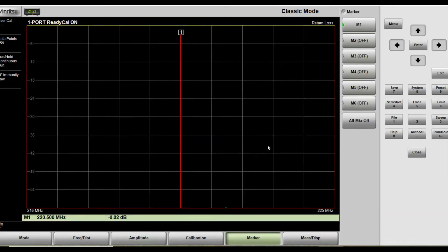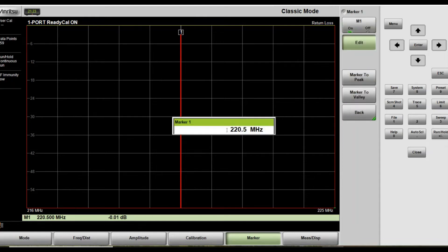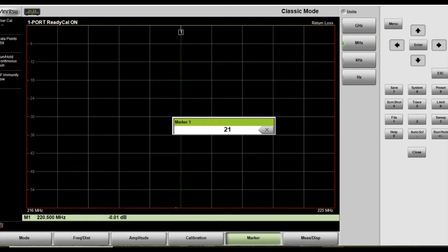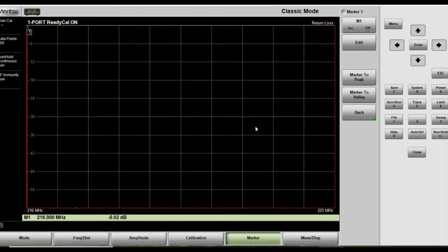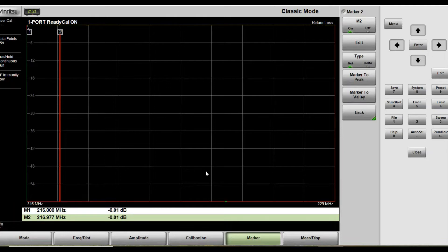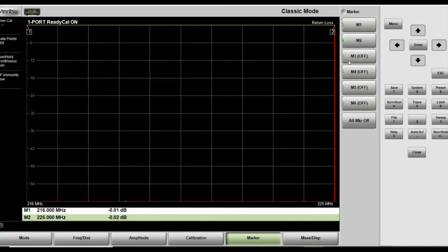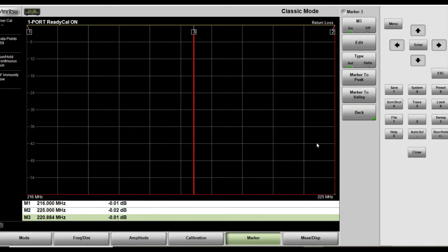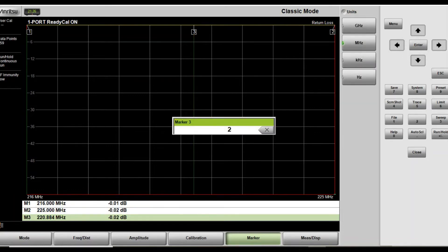The next thing to set up would be the markers. I will start with marker one. Normally, following Anritsu recommendations, you set up your start frequency. Press enter. The second marker would be the end frequency. Press enter. Now, for the third marker, you usually look at all your transmitter frequencies and you take the average. In my case, it's 217.25. Press enter.